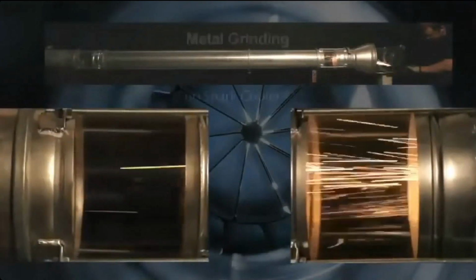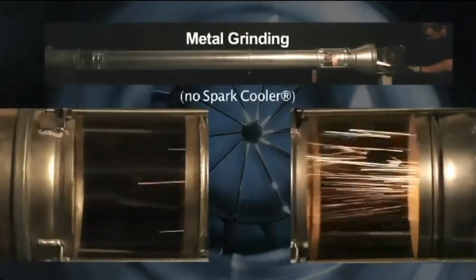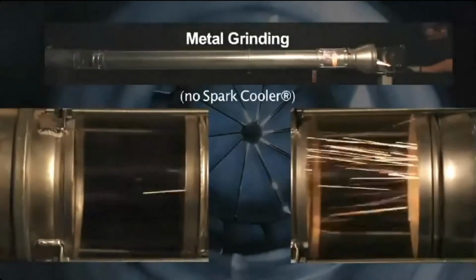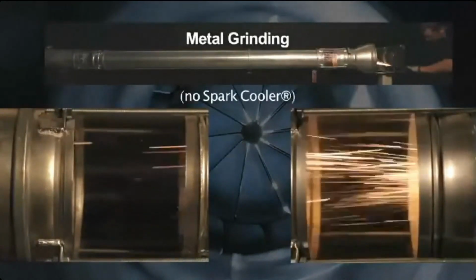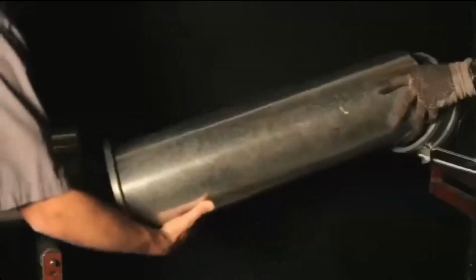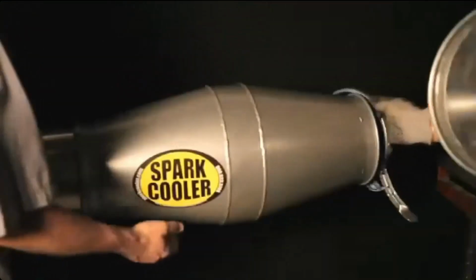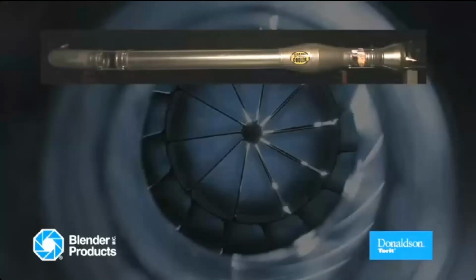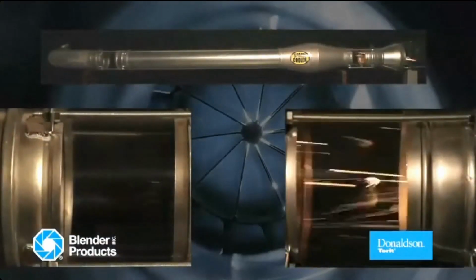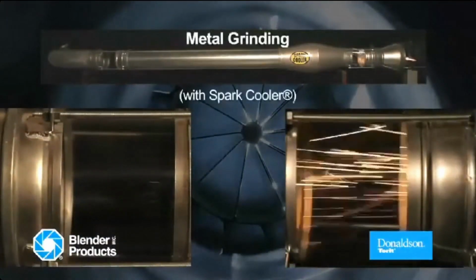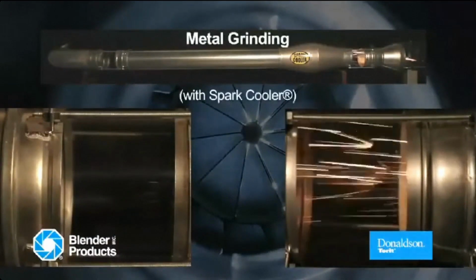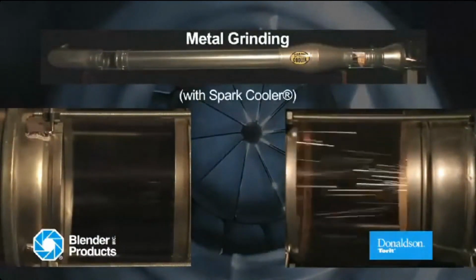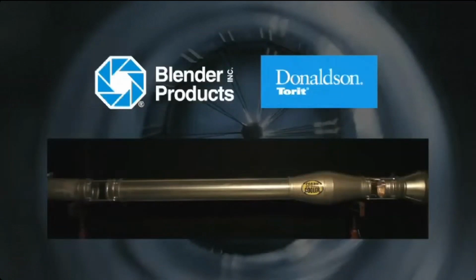All right, so what you're seeing here is a metal grinding application with no spark cooler. And then when we introduce the spark cooler to the system, you can see the application generating sparks going through the spark cooler, and out the other side of the duct, there are no sparks passing. So that just shows you the effectiveness of the spark cooler itself.